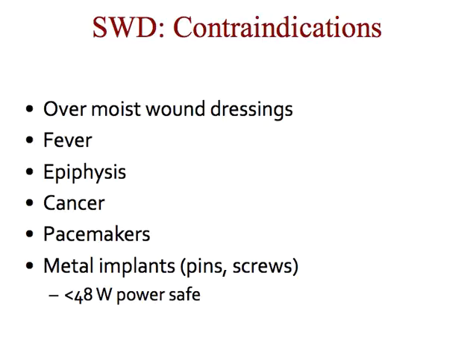Additional contraindications include fever, epiphysis — we don't want to change bone growth — cancer, pacemakers, and metal implants, typically screws and pins. However, you can use shortwave diathermy for mild or moderate heating in some metal areas if the watts are less than 48.